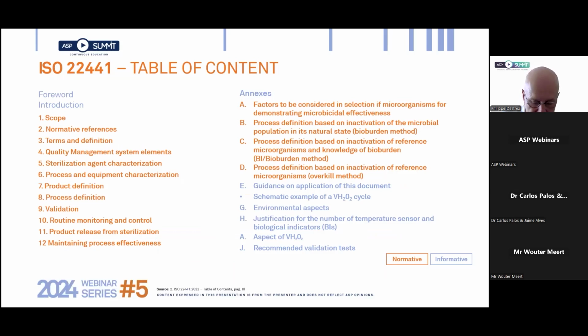The table of contents of ISO 22441 shows that process standards like 22441 span from the early stages of development, which are under the sterilizer manufacturer's responsibility, to daily routine operation by the healthcare facility. Like all sterilization process standards, ISO 22441 contains 12 normative paragraphs and some normative annexes also. As you can see from the color code, everything which contains normative requirements is in orange letters. The other paragraphs are informative, with just explanations pertaining to the normative paragraphs.